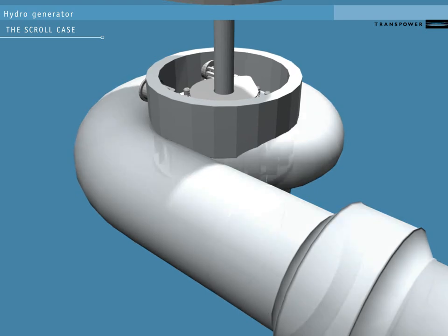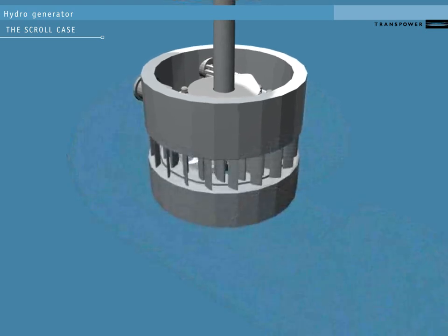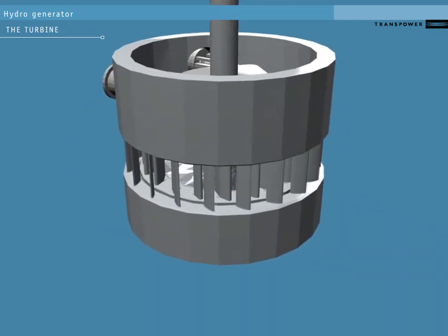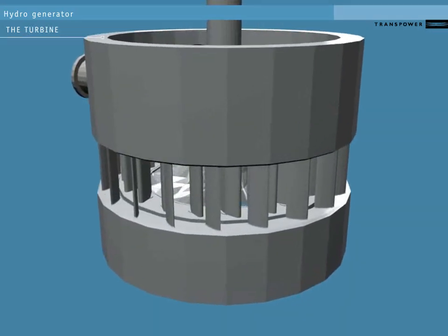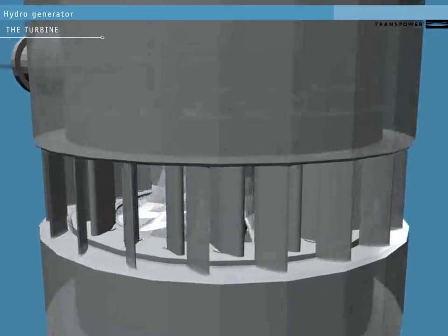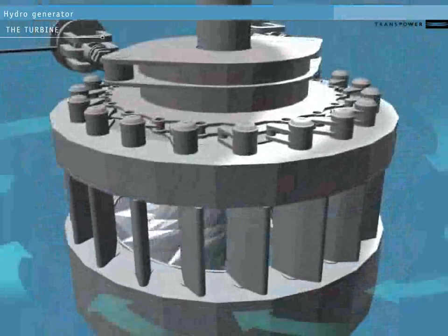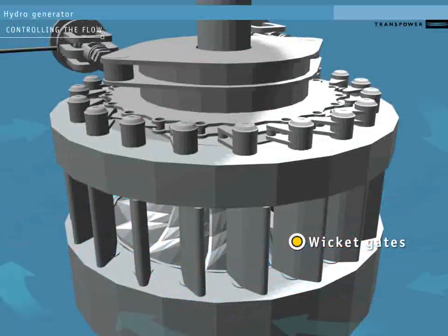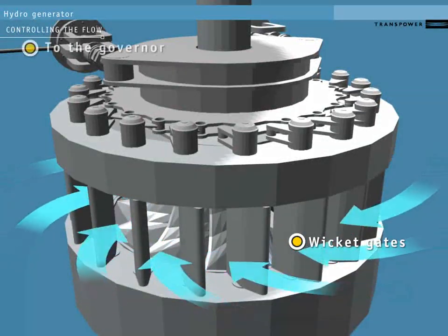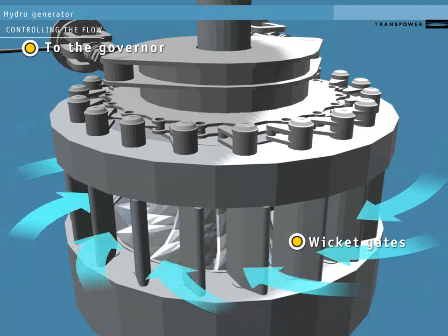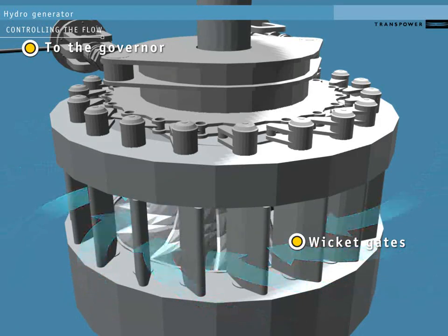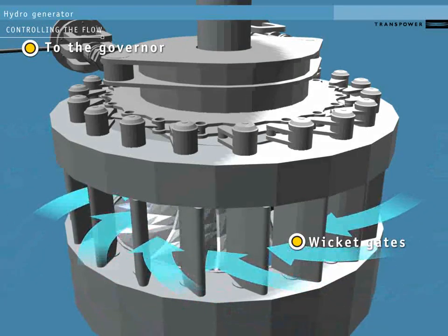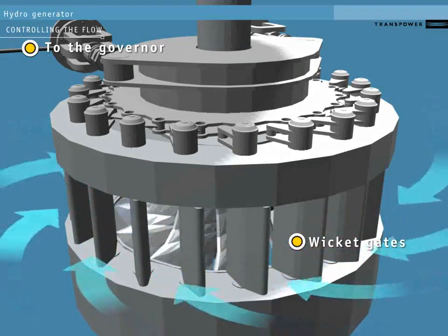Inside this scroll case is a set of vanes called the wicket gates. These control how water flows into the turbine. The wicket gates are controlled by an external governor system. This opens and closes them in response to conditions on the national grid.